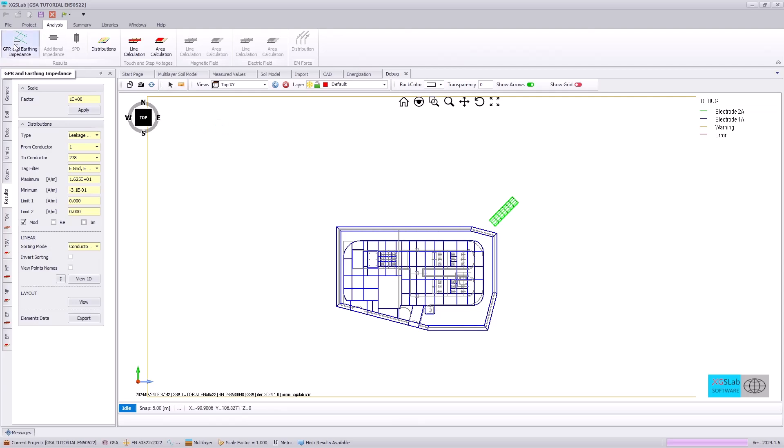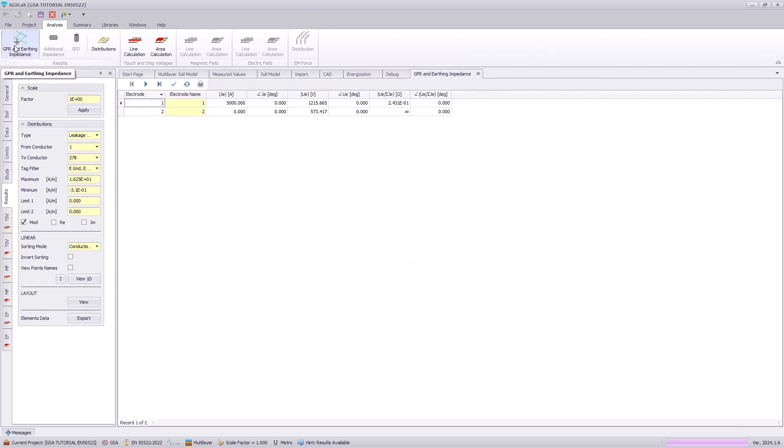And going to the GPR and earthing impedance icon, we can see 5000 amps is entered into electrode one and we have an impedance of 0.24 ohms.